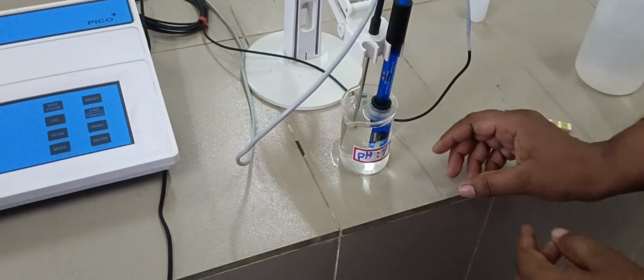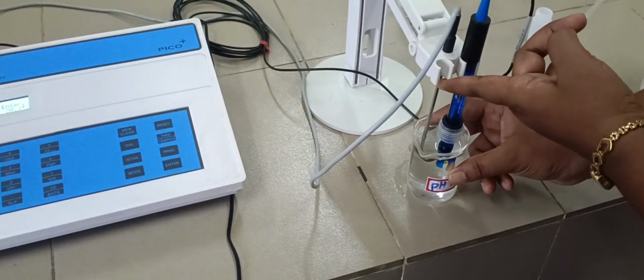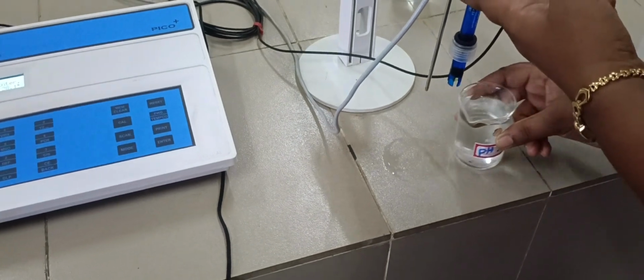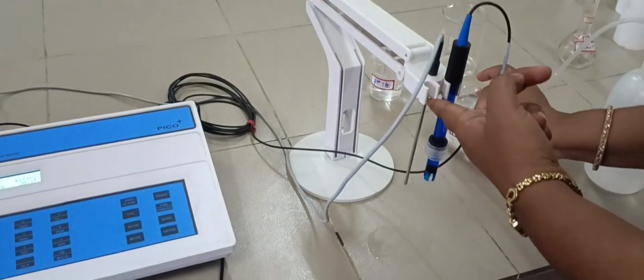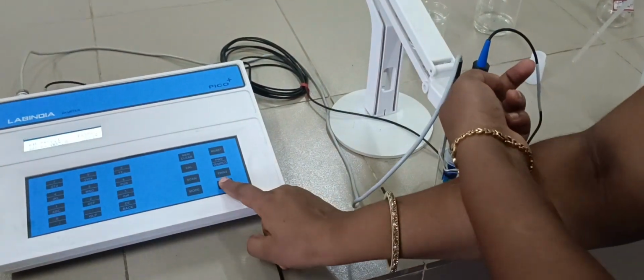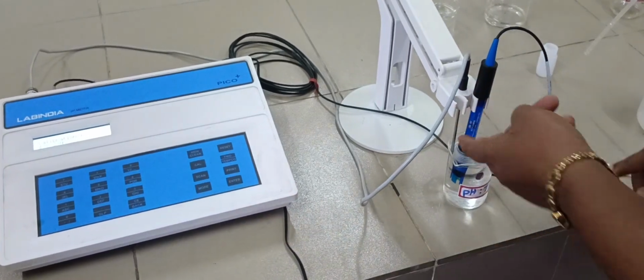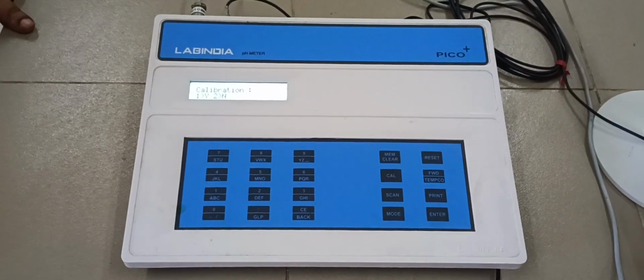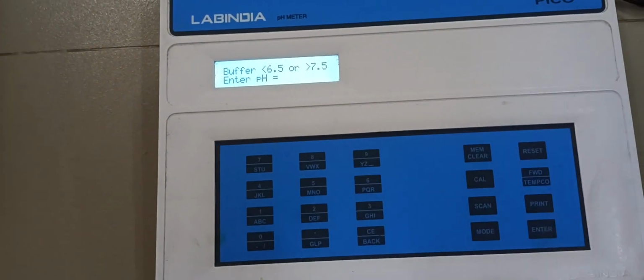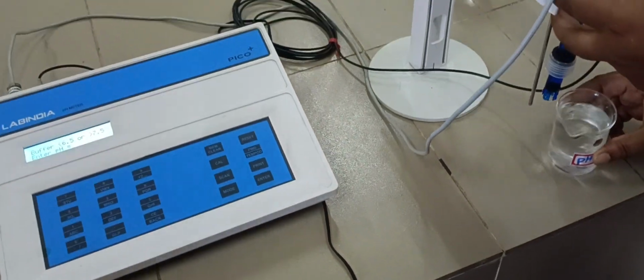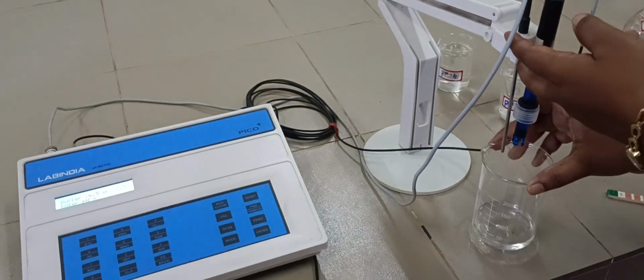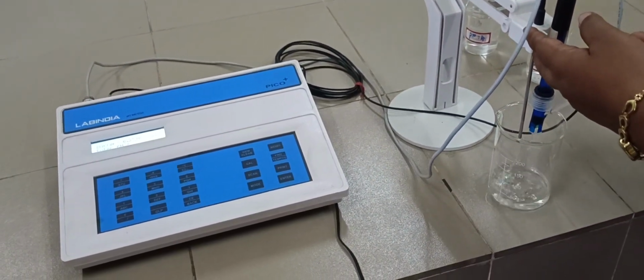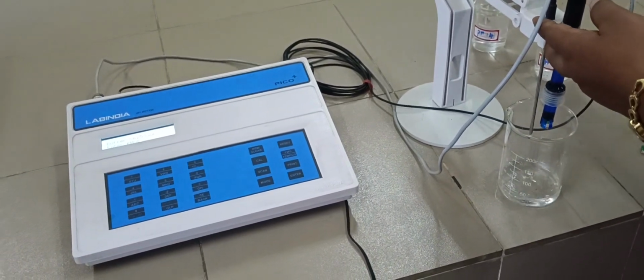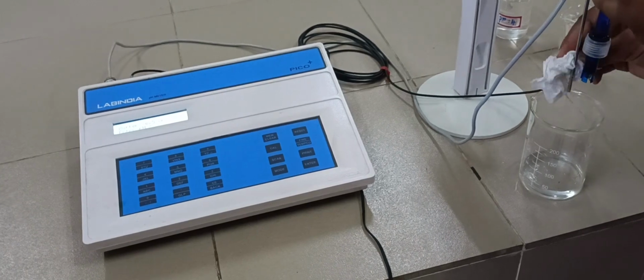After completion of buffer 7, wash the electrode with double distilled water. Each and every time we have to wash the electrode. Keep buffer 4, enter. Here also the same working principle applies: exchange of ions causes electrical flow that generates the voltage, which is converted to electrical signals. The pH was displayed.